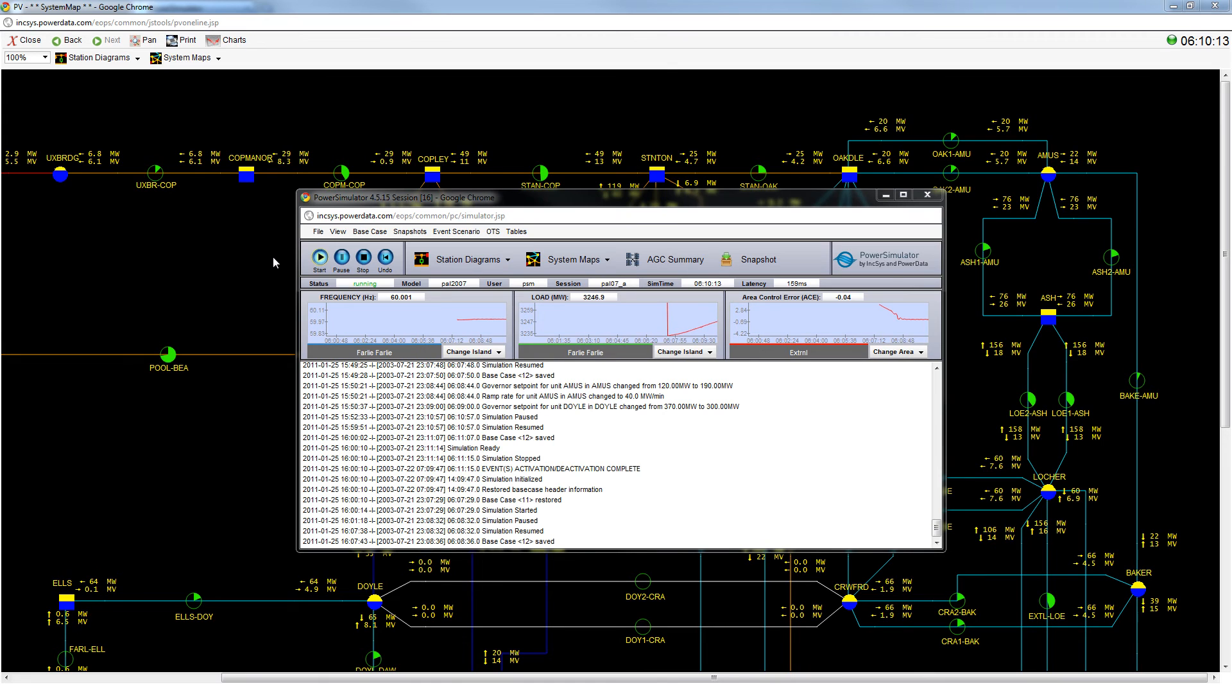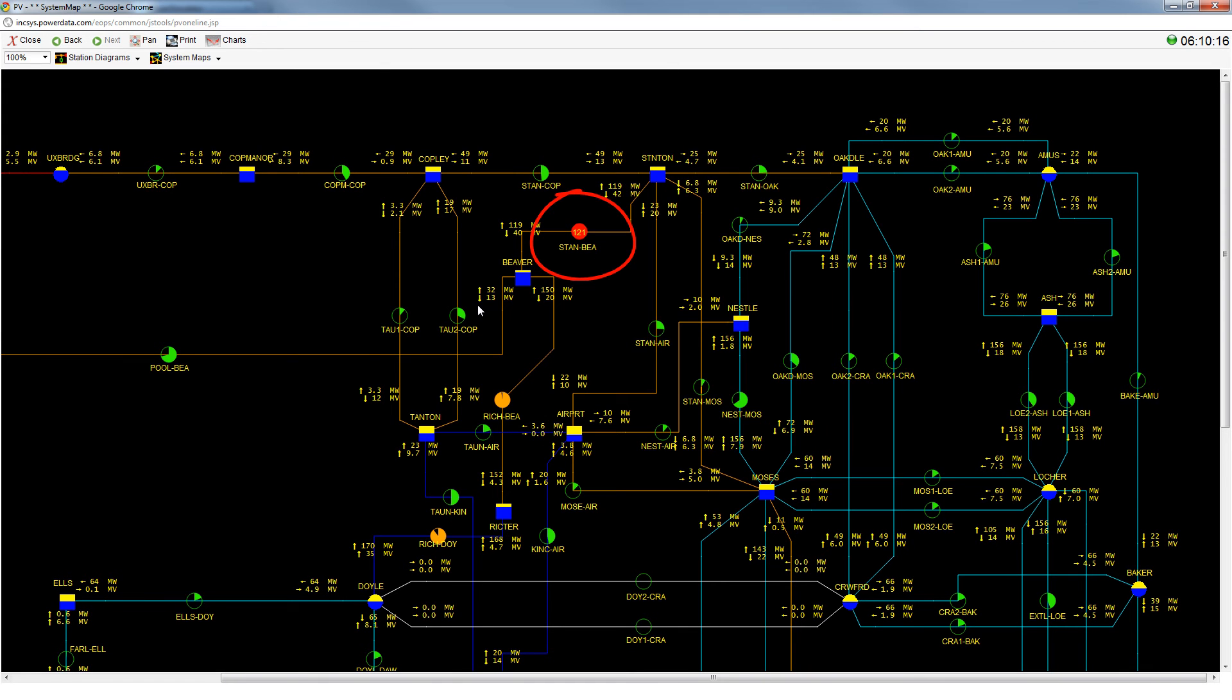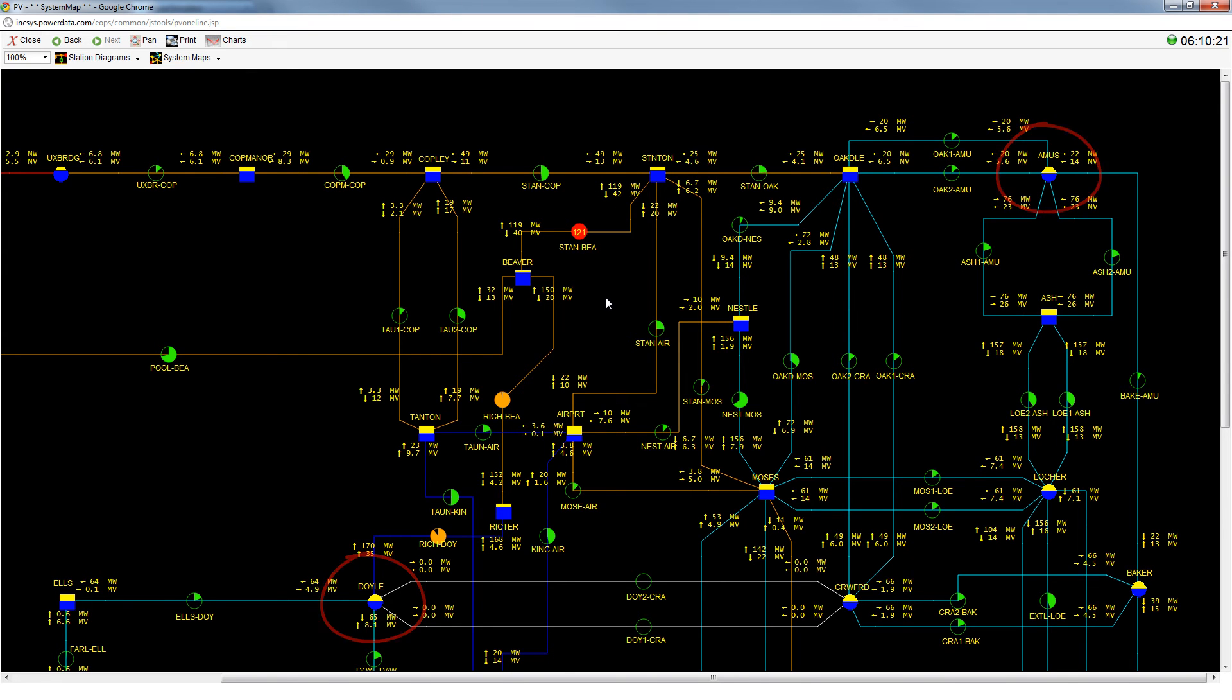Firstly, we have to identify the overload by monitoring the system map. Second, we identify the generators that we will be using for the redispatch. If the generator is electrically distant from the overloaded line, then the effect will be much smaller.